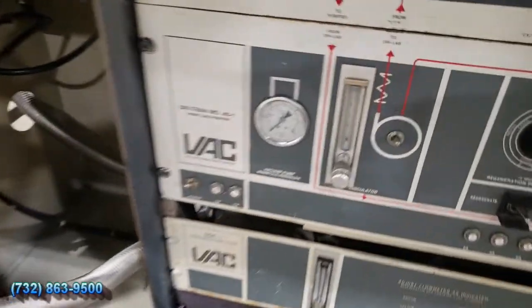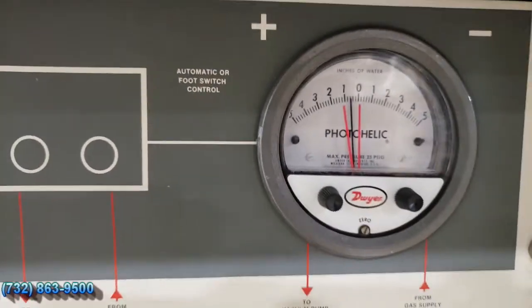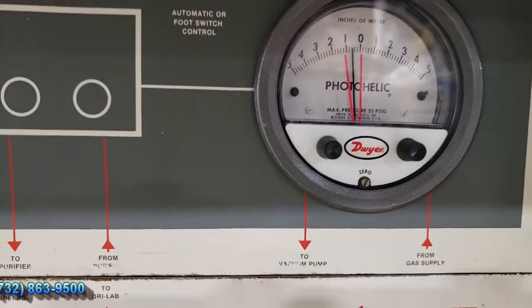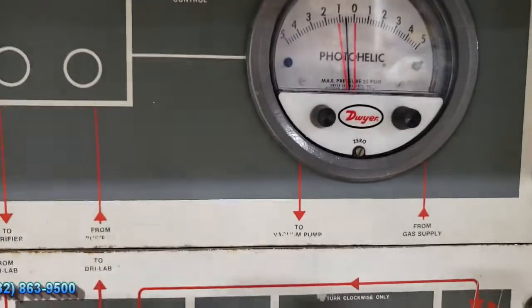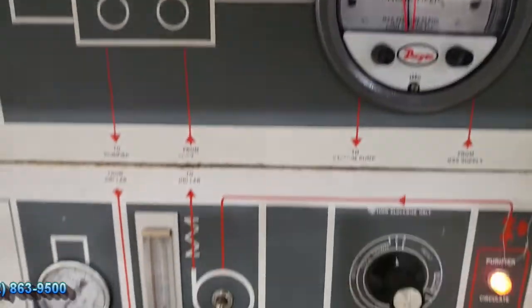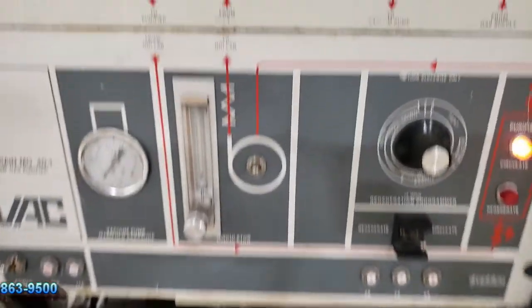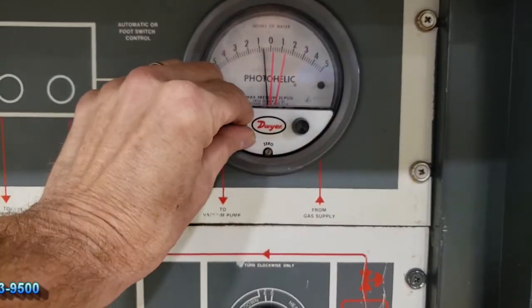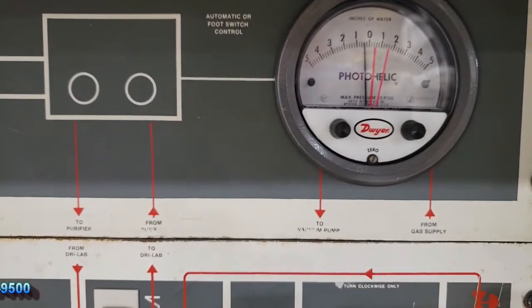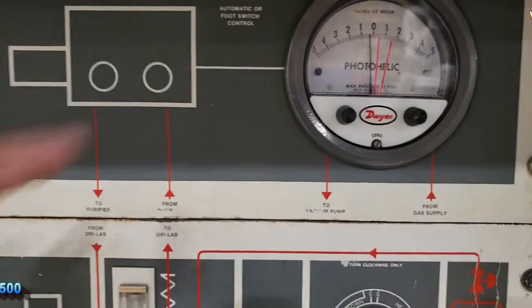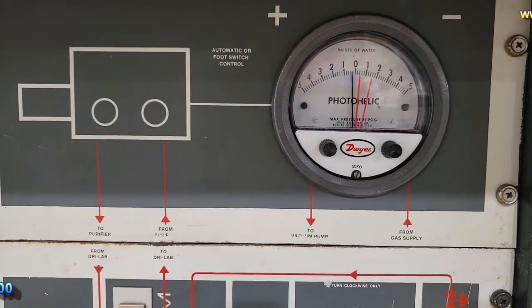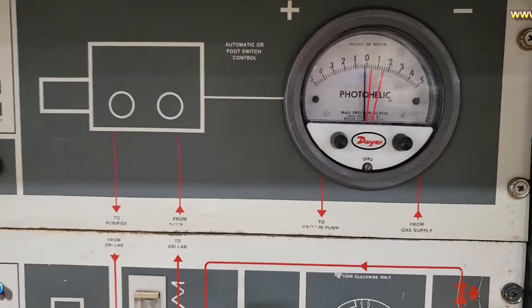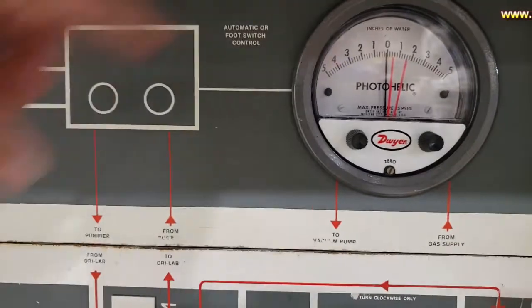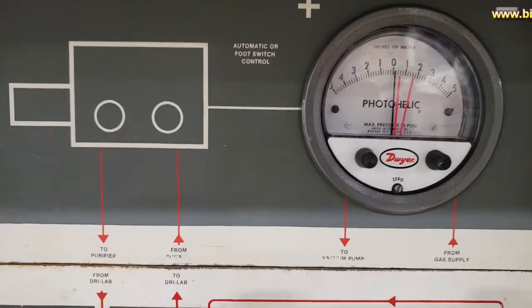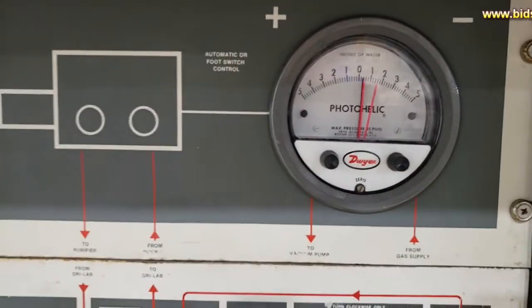This glove box has a range of plus or minus 5 inches of water. Right now I have the range set slightly positive. And if you want to reduce the pressure in the box, you could go ahead and set it to the right here. As you can see, there's a negative indicator here. And it'll automatically open a vacuum valve, a valve that's opened up to the vacuum manifold, and bring this down to a lower range using the vacuum pump. As you see, it's decreasing. Once it is inside the 2 red arrows there, it'll go ahead and shut off. And it tries to maintain its range, so you can hear the valve clicking on and off.